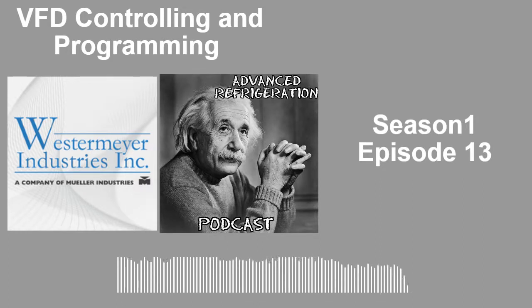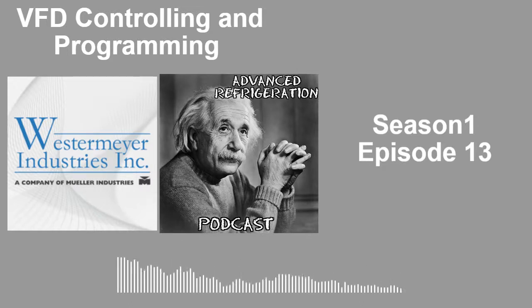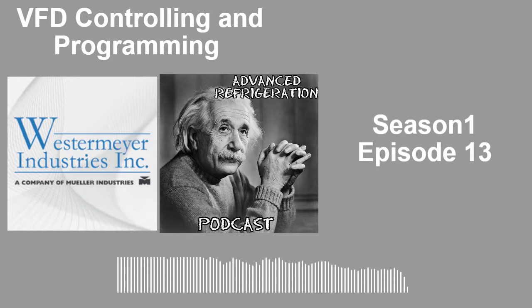What I was going to say is there's always usually some sort of enable, whether it be an enable and a forward command. We basically have to have three things for a drive. We have to have the voltage going to the drive. We have to have some sort of signal, whether it be generated on its own or a 0 to 10 or 10 to 0. And we also have to have a run command. We have to have some sort of relay output on our BAS system. You'll hear me say BAS every so often. It's a building automation system. So, just to cover all the basics.